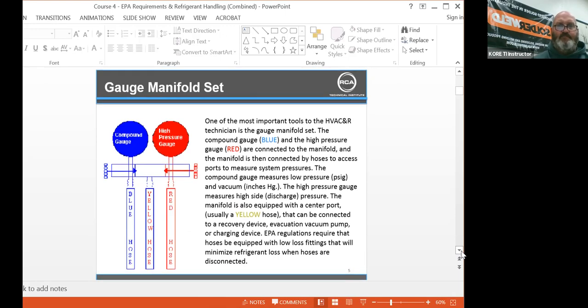Gauge manifold set. One of the most important tools to the HVACR technician is the gauge manifold set. The compound gauge, or blue, and the high side pressure or high pressure gauge, red, are connected to the manifold. The manifold is then connected by hoses to access ports to measure system pressures. The compound gauge measures low pressure and vacuum. The high pressure gauge measures high side discharge pressure. The manifold is also equipped with a center port, usually a yellow hose, that can be connected to a recovery device, evacuation pump, or charging device.